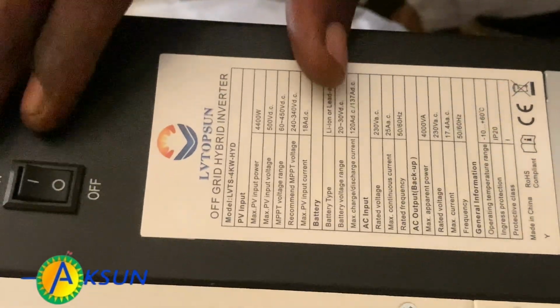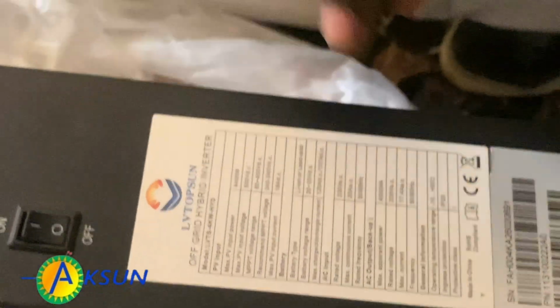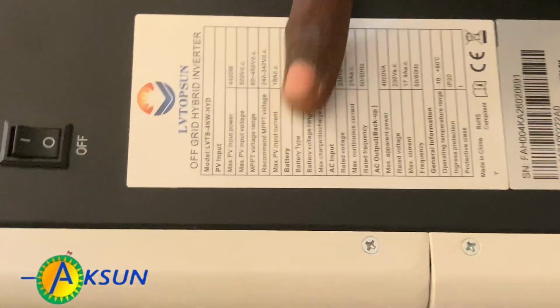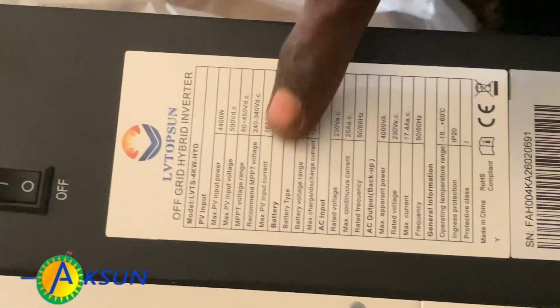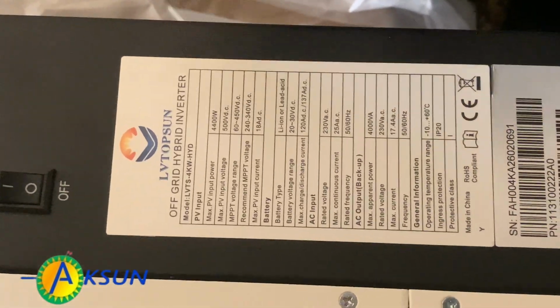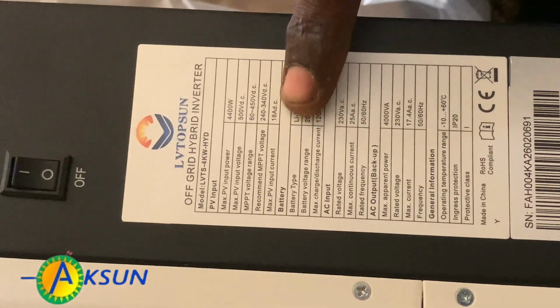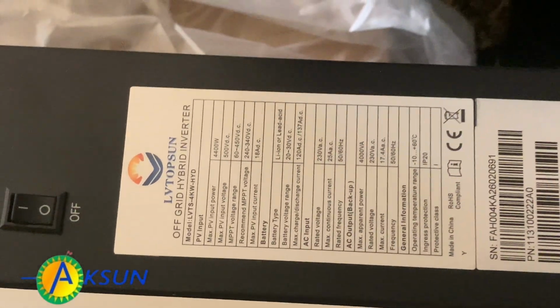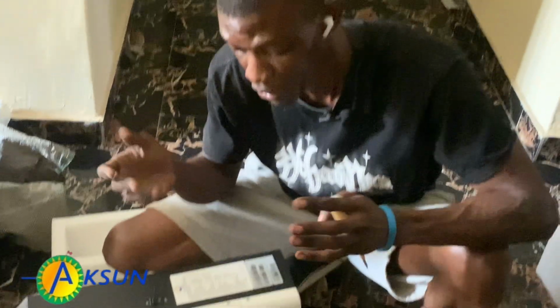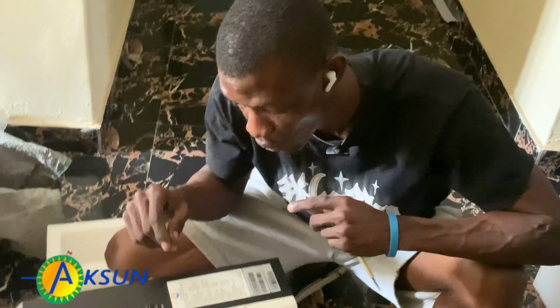It comes with a high frequency MPPT controller, which is what I always emphasize for any type of inverter—the recommended MPPT voltage is very, very important. For the current, we have a maximum of 18 amps, which means you can use 700 watts or 600 watts of PV, giving 14 to 15 amps of charging current overall.